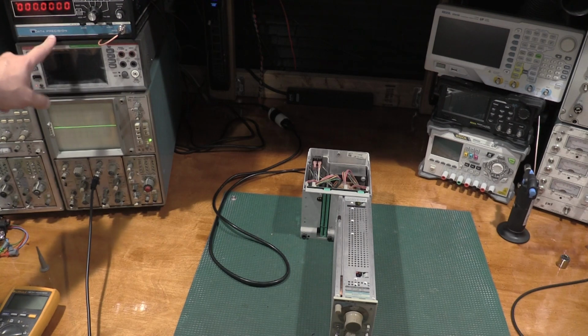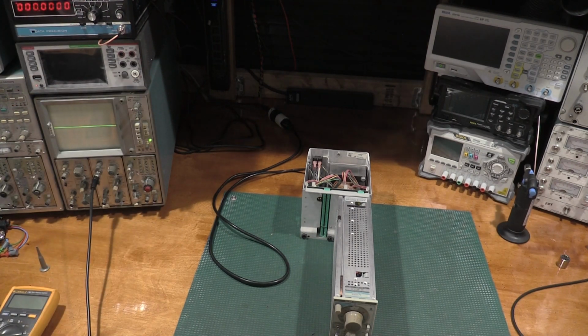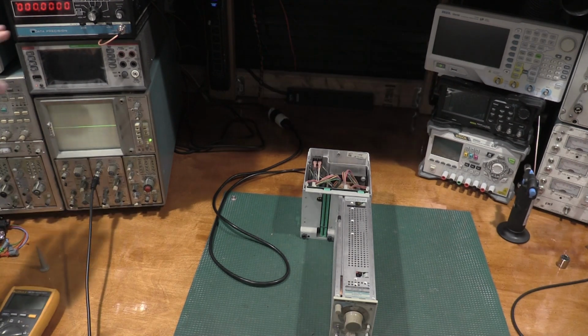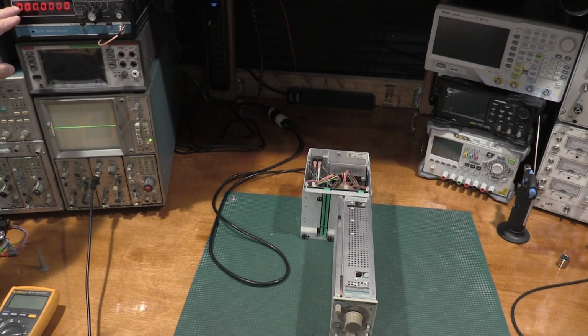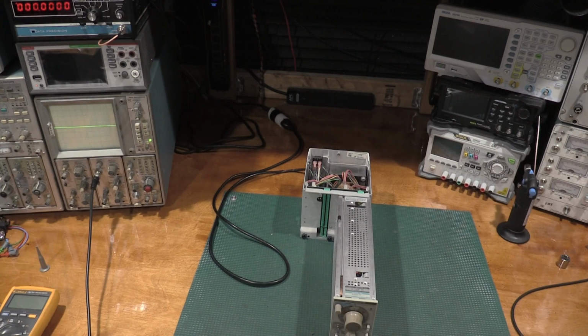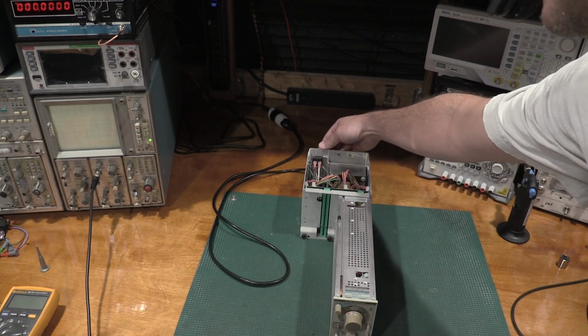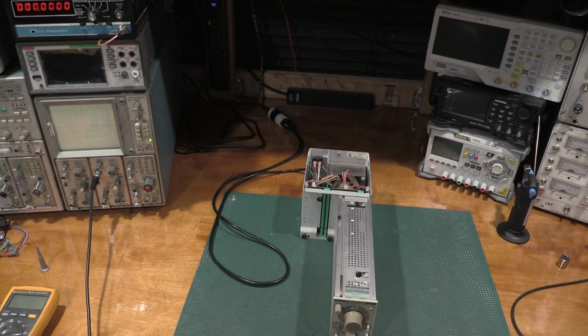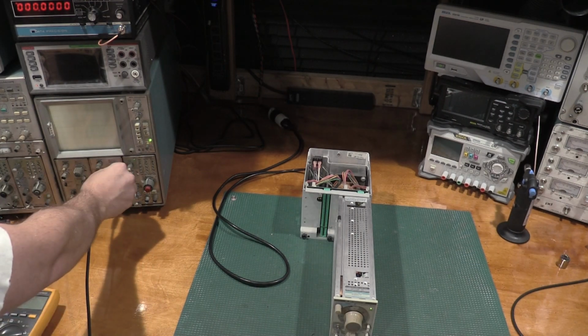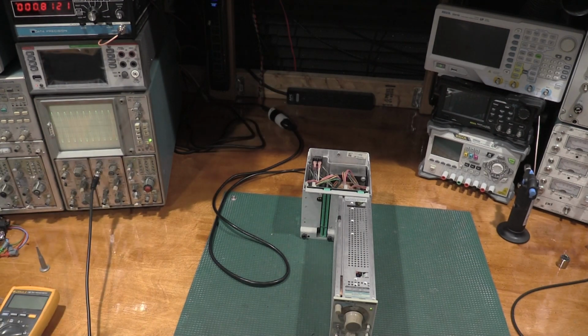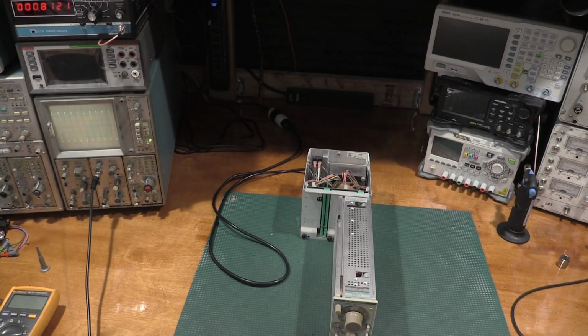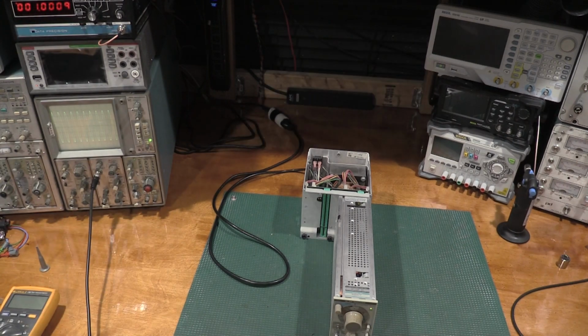frequency is bouncing around. The gate time on this frequency counter is quite long. It's 10 seconds. So it'll give us a very accurate frequency, but if you watch the dot here, it'll take a while to cycle. I have the unit set up for 1 kilohertz. And let's go. Actually, let me go around here. I do not know how fast this will start. Quite quickly, actually, apparently. Don't pay attention to the first cycle, so we need gate time to go. Let's see, it just gated, so we're at 1009. We'll see if it bounces around.